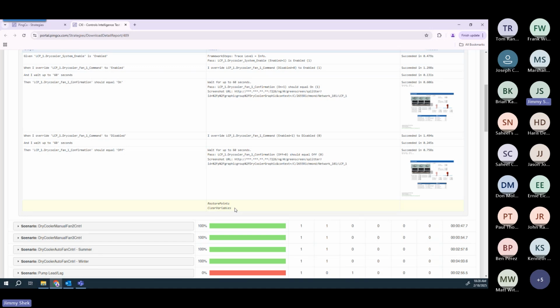Or in the cases of when you're overriding something, being able to relinquish that after you're done with the test, right? Sometimes when you're trying to run these tests manually, you're going out and overriding 4, 5, 6, 7 units. At the end of the test, you have to go back and remember to relinquish those values, right? Sometimes, hey, out of the 7 you missed one, now your system is no longer in an auto state. So PingCx takes that out of the equation, all the user error. It's tracking it automatically and putting everything back to where it found it.